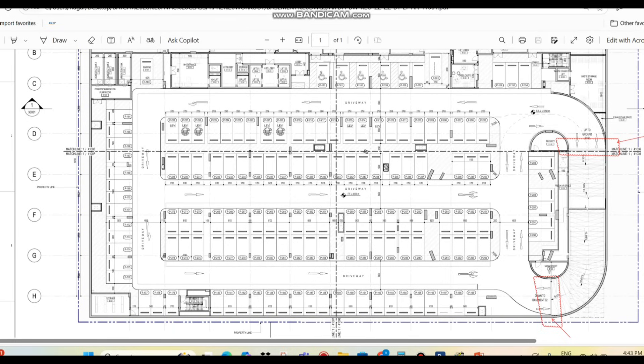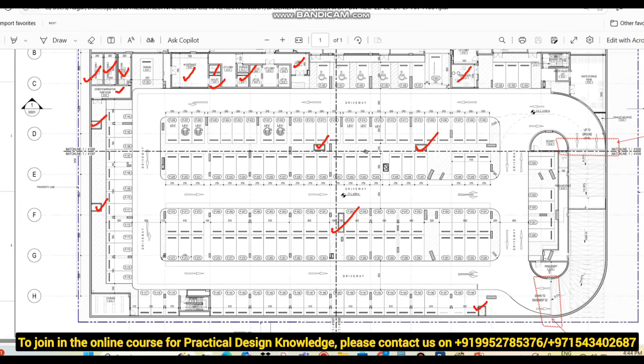The very first important thing is finding the proper area for the calculation. You can see fixed structures like shafts, and multiple rooms such as a domestic irrigation pump room, domestic water supply tank, irrigation tank, entrance area, lift shafts, VIP lift, lobby area, garbage chute room, lift lobby, and waste storage room. We do not need to consider these types of enclosed spaces when calculating the car park ventilation area.